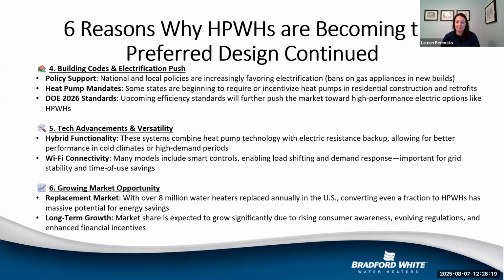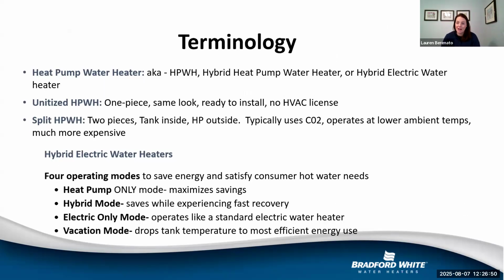But last, for the reasons why heat pump water heaters are becoming preferred designs, there is growing market opportunity. In the replacement market, over 8 million water heaters are replaced annually in the United States. Converting even a fraction of those to heat pump water heaters has massive potential for energy savings. We also have long-term growth. Market share is expected to grow significantly due to rising consumer awareness, evolving regulations, and enhanced financial incentives. I know for the engineers on the call, sometimes it's a bit of a challenge when your building owner says, we want X, but that doesn't necessarily make sense for the design, but you want to comply with the building owner so you get the job. So I think that's one of the challenges too: what are people hearing and why do they want to install it?